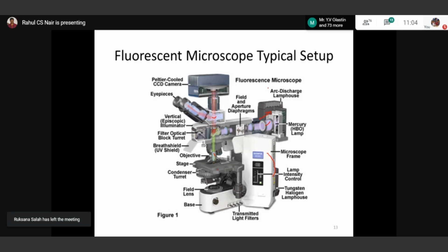Then the emitted light again goes back above. You can see it as red, and here is the CCD camera, and you can also view it through the eyepiece. Almost all microscopes have different optical ports through which you can capture or see the image. So there are ports with 100% transmittance, 80% transmittance, like that. You can attach multiple cameras to get different images of interest. So this is the arrangement basically. The three important main parts are the optical system, the light source, and the detector. We will be concentrating further on these three important concepts for a fluorescent microscope.